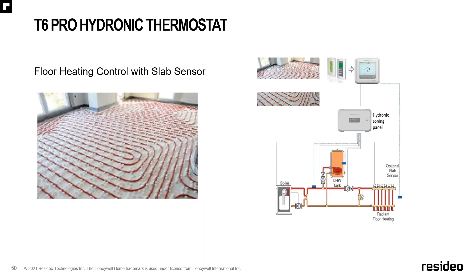The unique benefits for this T6 Pro hydronic: you can set max floor limits to protect the floor from damage, and minimum floor limits to enhance comfort. It has antifreeze temperature protection and boiler short cycling protection built in, as well as regular programming and vacation hold settings. So if a homeowner is using this in a vacation home, or if they're a snowbird, they can have that set up. There's also an economy mode setting that overrides the floor low limit setting during away and sleep periods for energy savings—a few added features for hydronic heating systems with this thermostat.